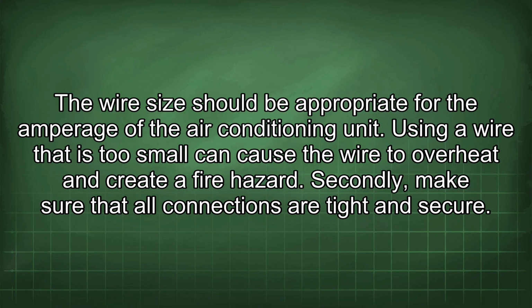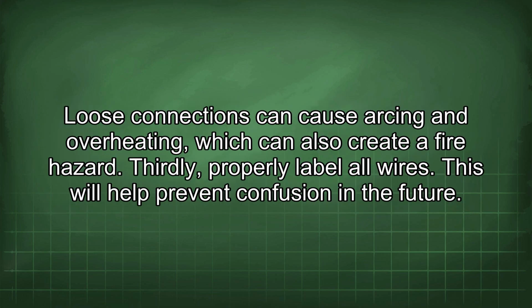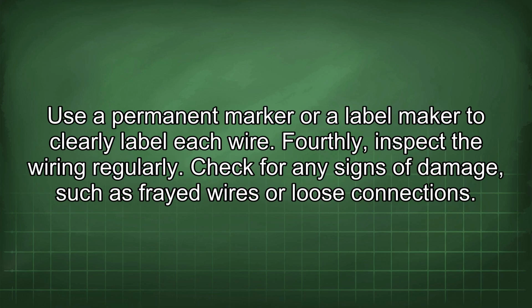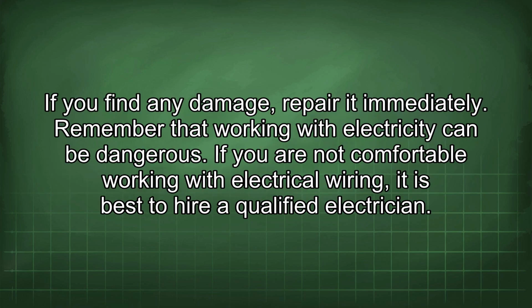Secondly, make sure that all connections are tight and secure. Loose connections can cause arcing and overheating, which can also create a fire hazard. Thirdly, properly label all wires. This will help prevent confusion in the future. Use a permanent marker or a label maker to clearly label each wire. Fourthly, inspect the wiring regularly. Check for any signs of damage, such as frayed wires or loose connections. If you find any damage, repair it immediately. Remember that working with electricity can be dangerous. If you are not comfortable working with electrical wiring, it is best to hire a qualified electrician.